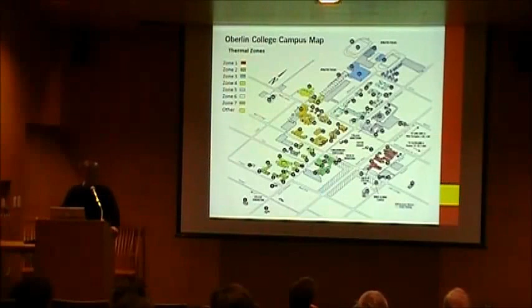The green is where the conservatory is. The light blue is one of those I talked about before, where maybe you could take the north residence area and heat all of those residence halls in the wintertime with a ground source geo-exchange system, and use the cooling load from the science complex to offset the heating load to recharge the well field in the wintertime, keeping the heating load along with the rest of the buildings in orange on a smaller centralized loop that could be fired with steam from natural gas, or a local source of biomass or biogas, or some other technology that hasn't been invented yet.